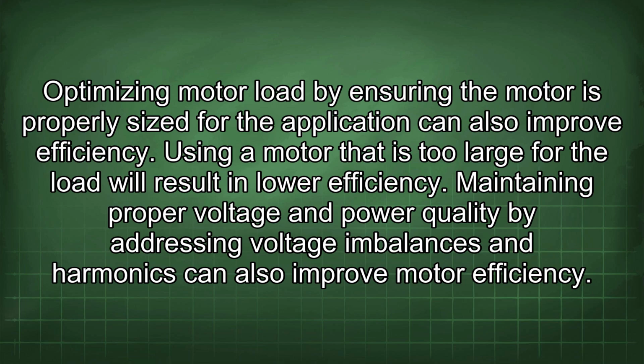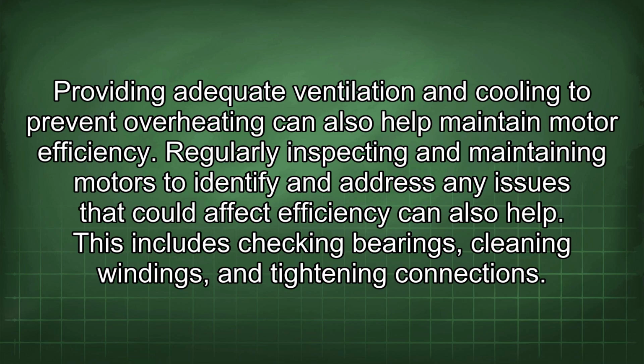Optimizing motor load by ensuring the motor is properly sized for the application can also improve efficiency. Using a motor that is too large for the load will result in lower efficiency. Maintaining proper voltage and power quality by addressing voltage imbalances and harmonics can also improve motor efficiency. Providing adequate ventilation and cooling to prevent overheating can also help maintain motor efficiency. Regularly inspecting and maintaining motors to identify and address any issues that could affect efficiency can also help. This includes checking bearings, cleaning windings, and tightening connections.